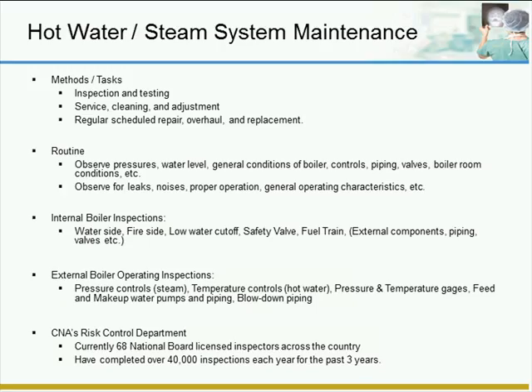The fireside inspection is a visual inspection for soot, bulging, warping, overheating, and overall condition of the fireside of the unit. You want to check for any cracks in the refractory, any cracks on the tube sheet, improper combustion, excess flue gas, and signs of leaking in the stack exhaust. The low water cutoff should be taken apart, and all external piping should be inspected visually.